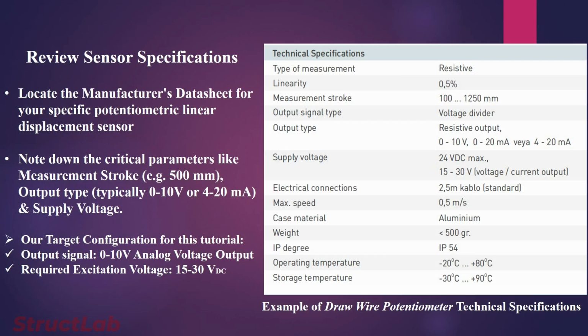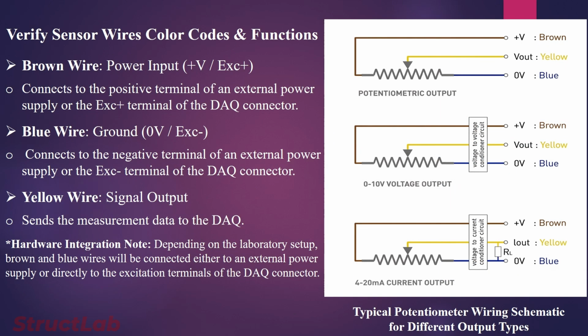Step 1. Locate and review the manufacturer's datasheet for your specific potentiometric linear displacement sensor. Before making any electrical connections, it's important to note key parameters, namely, the physical measurement stroke, the available output options, and the required supply voltage. For this specific tutorial, we'll be working with a 0 to 10 volt analog output model, which needs 15 to 30 volts DC excitation.